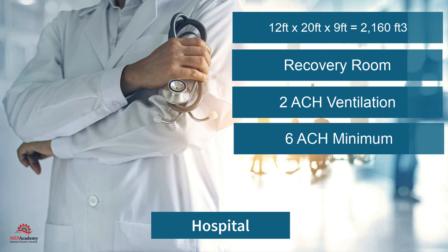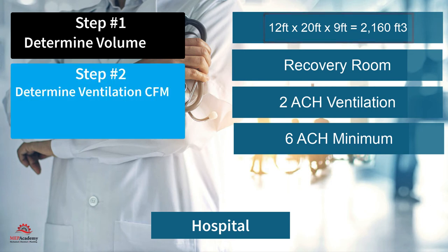Step 1 is to determine the volume of the room, which is 2,160 cubic feet. Step 2: determine the required ventilation CFM. CFM equals two air changes per hour times 2,160 cubic feet divided by 60, giving CFM equals 72.